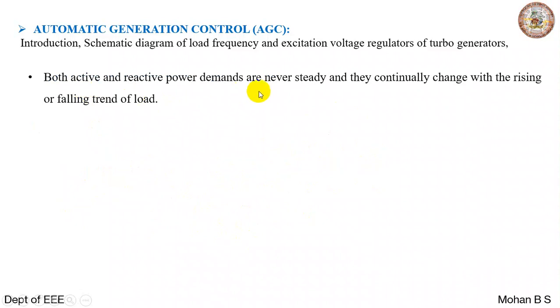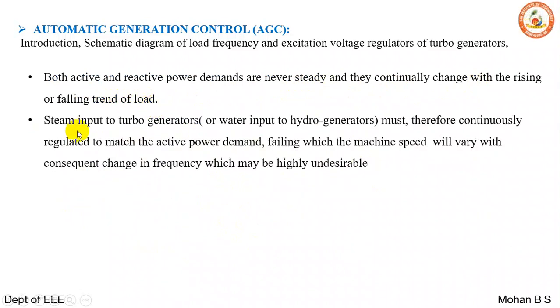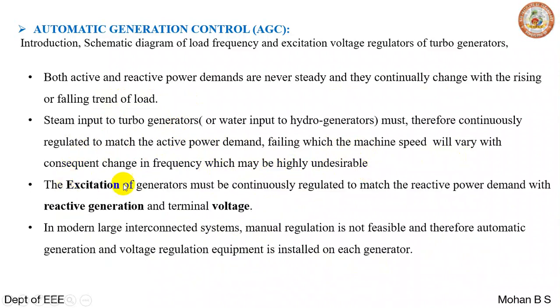Both active and reactive power demands are never steady and they continually change with the rise or fall trend of load. Steam input to the generators must therefore continuously regulate to match the active power demand, failing which the machine speed will vary with consequent change in frequency, which might be highly undesirable. The excitation of the generator must also be continuously regulated to match the reactive power demand. In modern large interconnected systems, manual regulation is not possible, and therefore automatic generation and voltage regulator equipment is installed in each generator.